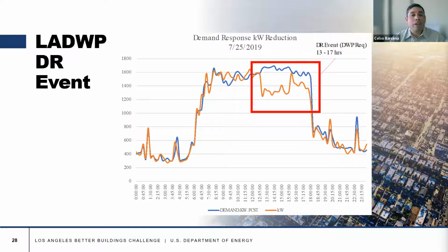Okay, I'm kind of a nerd, I guess, I get really excited looking at graphs, and I think this one tells an exciting story. This graph was produced as part of one of our demand response participations at the US Bank Tower. The blue line shows the expected KW use or demand for the day, and the orange line shows the actual KW consumption. DWP had requested that we participate in a demand response event starting sharp at 1 p.m., which is why the orange line drops abruptly there. That's really good news, it means our measures are taking effect and we're able to reduce the electrical load in the building.